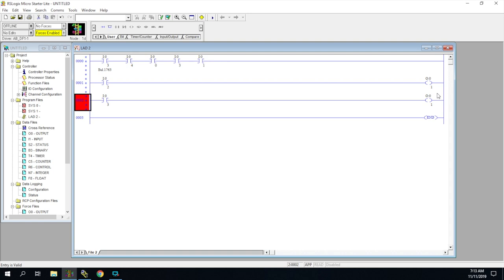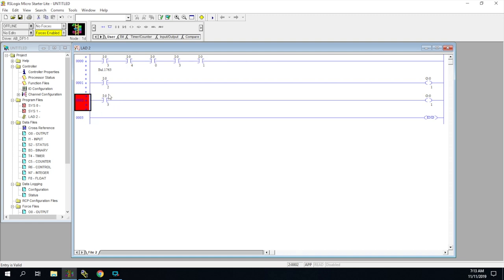But that's not what will actually happen. What will happen is rung number one will turn on this output, while rung number two will turn it off. Because this input number two here will be true, it will energize our output over here. And then as the PLC scans to the next rung, it's scanning, it's going through one rung at a time, all the way down. It will see that this is open, so it's not true at this point. And it will actually see that we need to turn off the output zero slash one, so we'll turn it off. So this will happen super fast. You won't even see it.